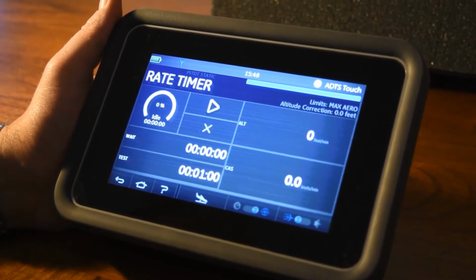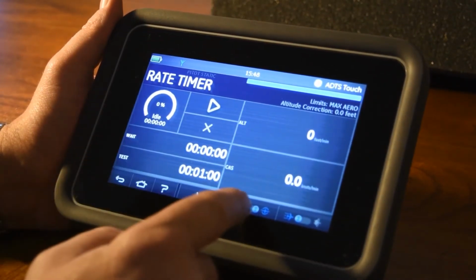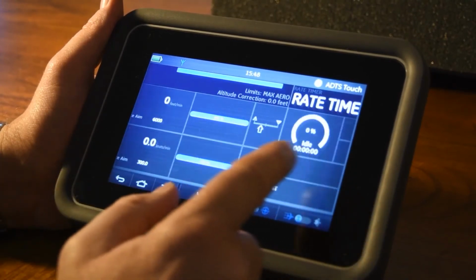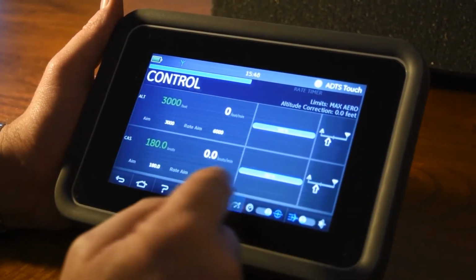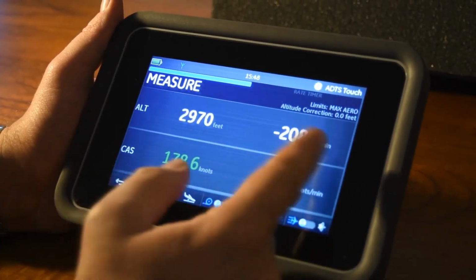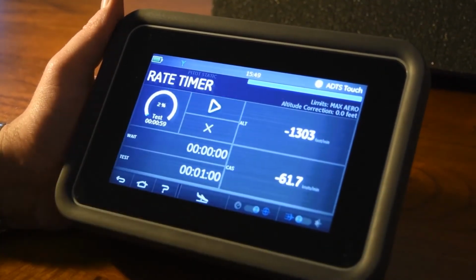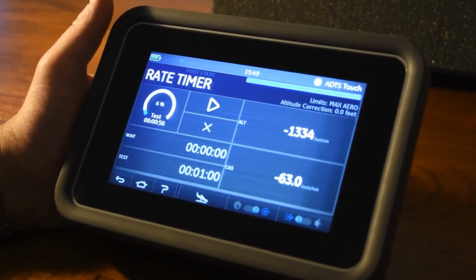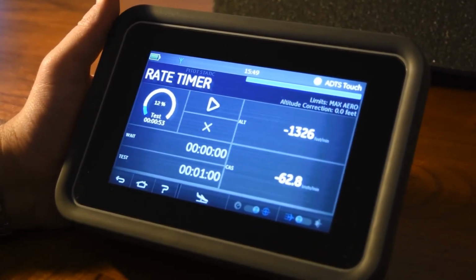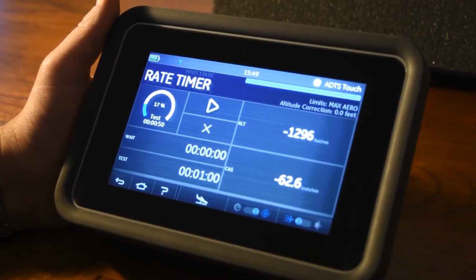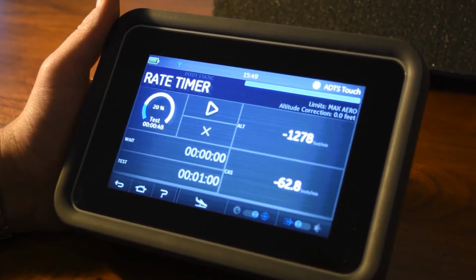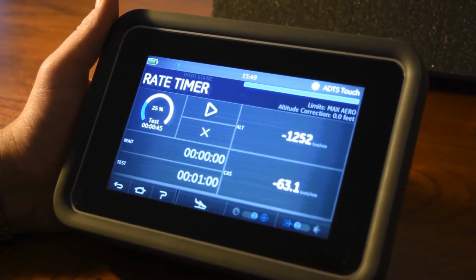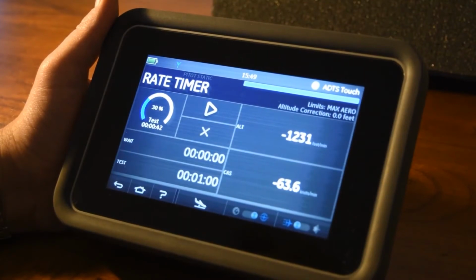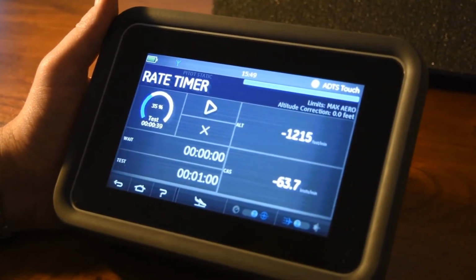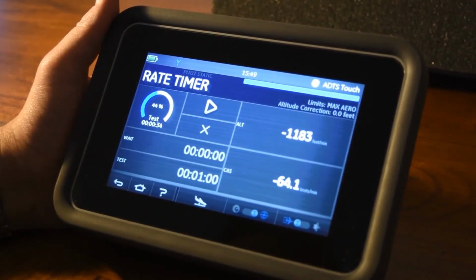So things are fine. Okay, so what I'll do now is I'll go back into measure mode for the leak test, and it will start leaking, I think, pretty fast, and you can see straight away. So I'll swipe over and I'll start my leak test. That's a pretty bad leak. I can see that it's within the parameters that are okay, so it's not greater than 6,000 feet per minute, which is the limit for my device that I'm testing.